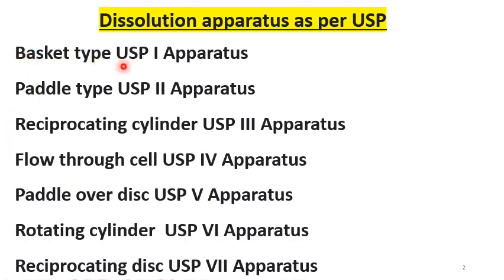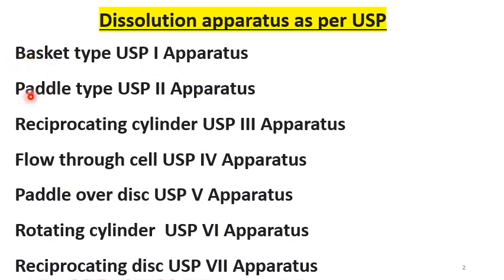Don't get confused between the reciprocating cylinder and reciprocating disk — reciprocating cylinder is USP 3 and reciprocating disk is USP 7. This basket type apparatus, USP 1, is also called rotating basket. Don't confuse rotating basket with rotating cylinder. Mainly for oral solids, apparatus up to type 4 are used — basket, paddle, reciprocating cylinder and flow-through cell. Out of these, paddle is the most widely used apparatus for oral solids.